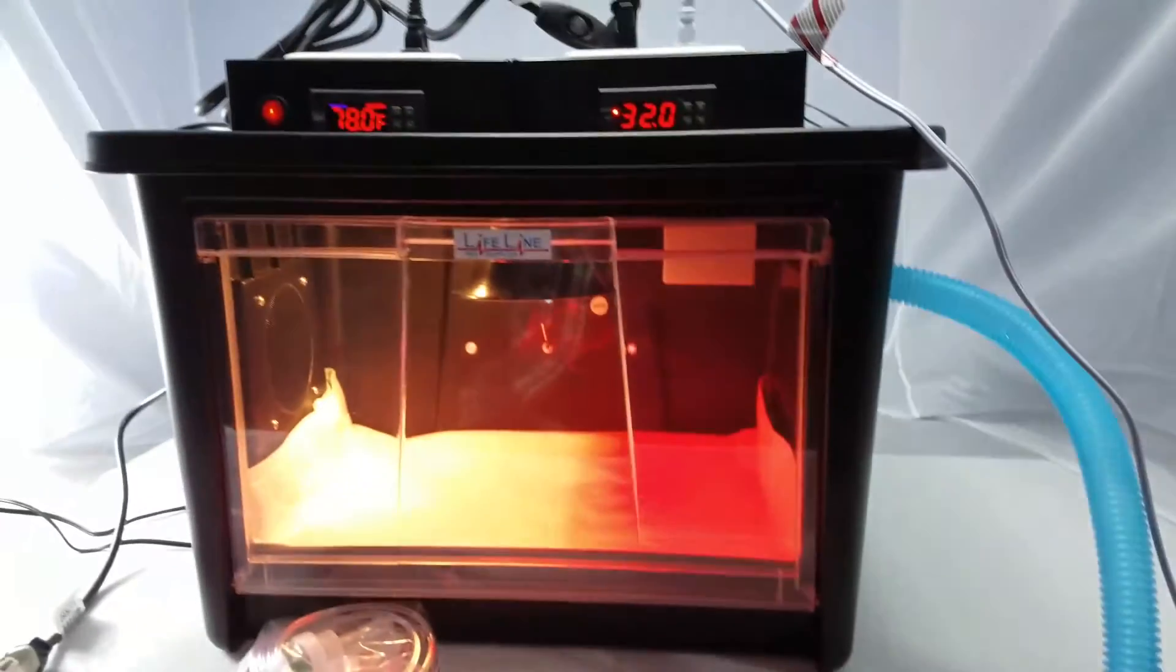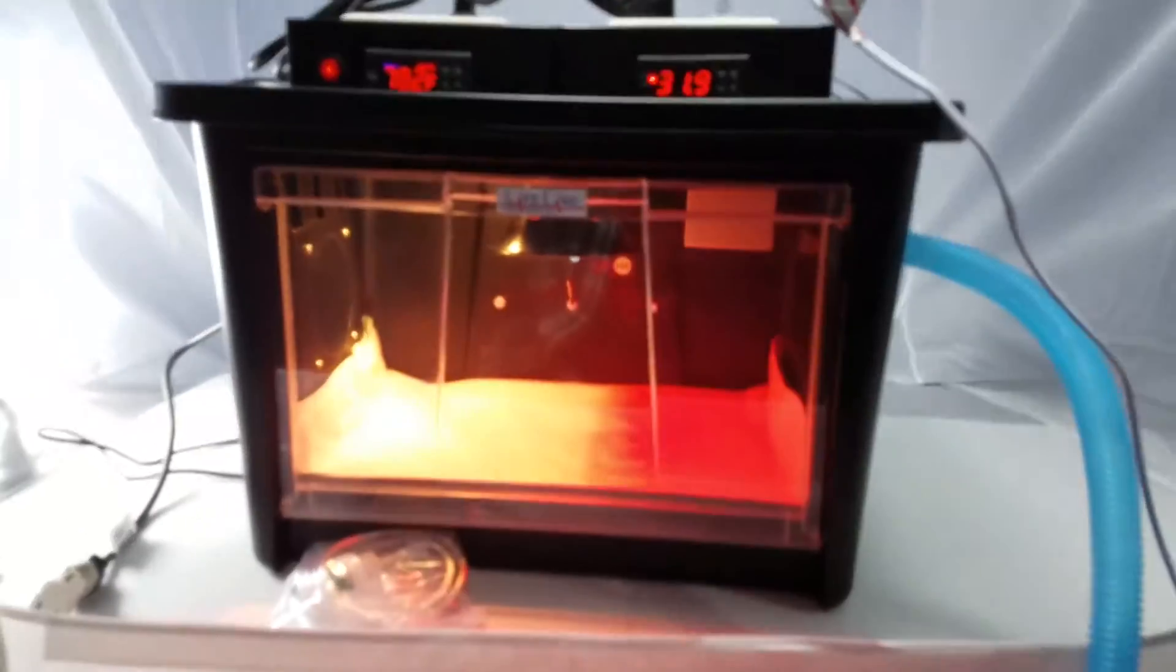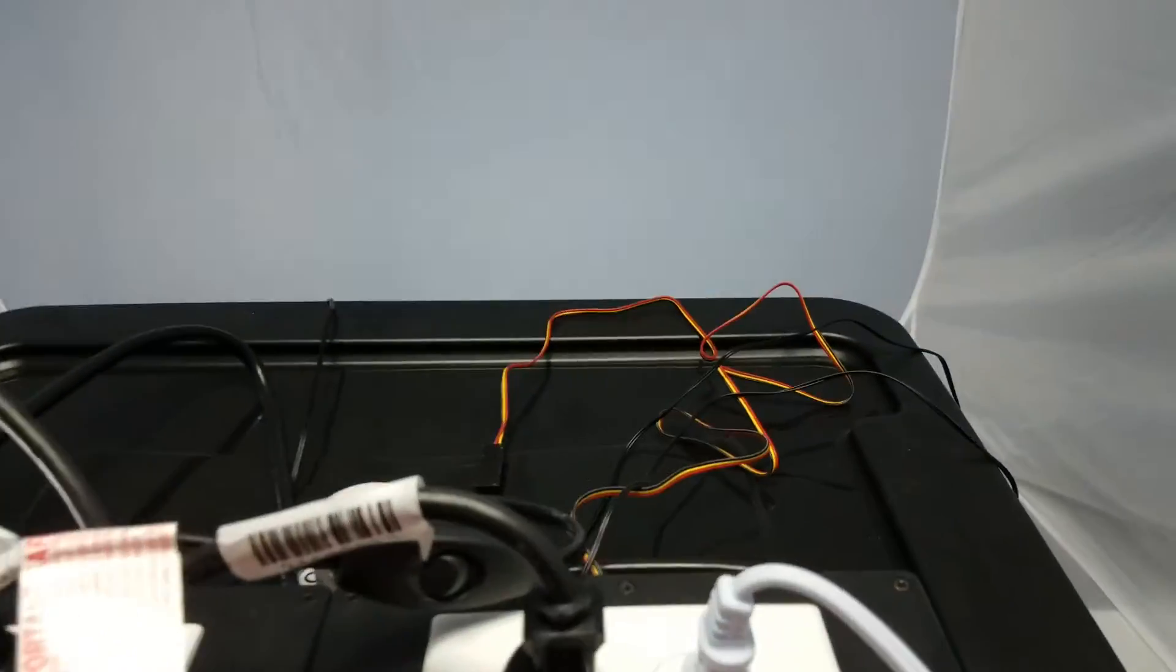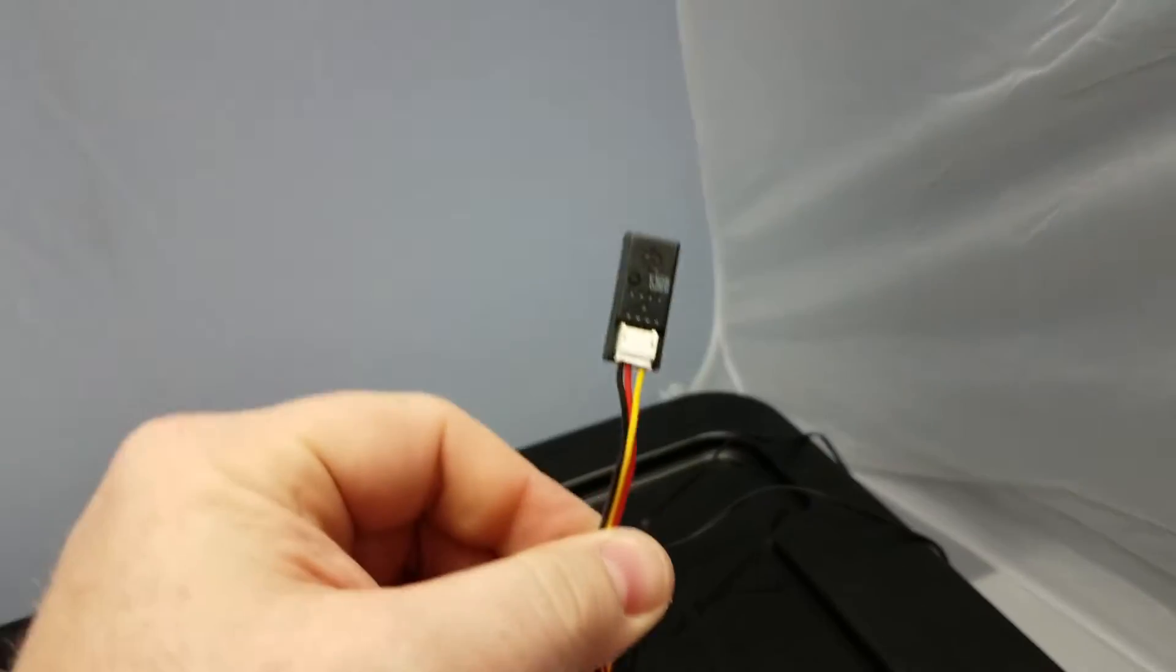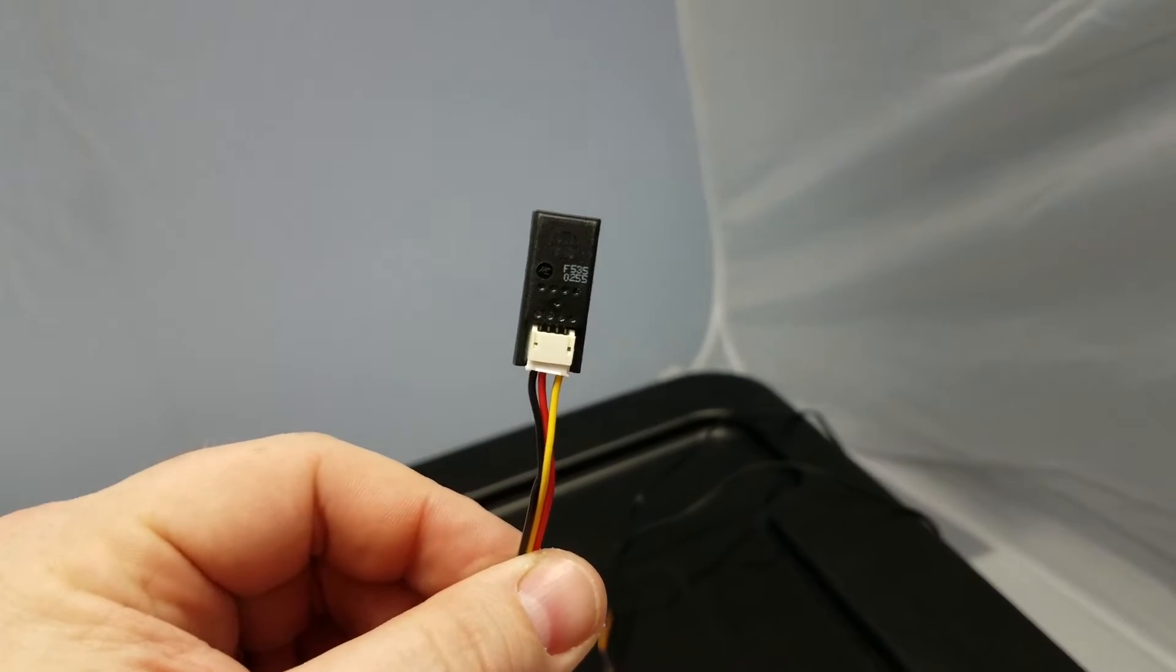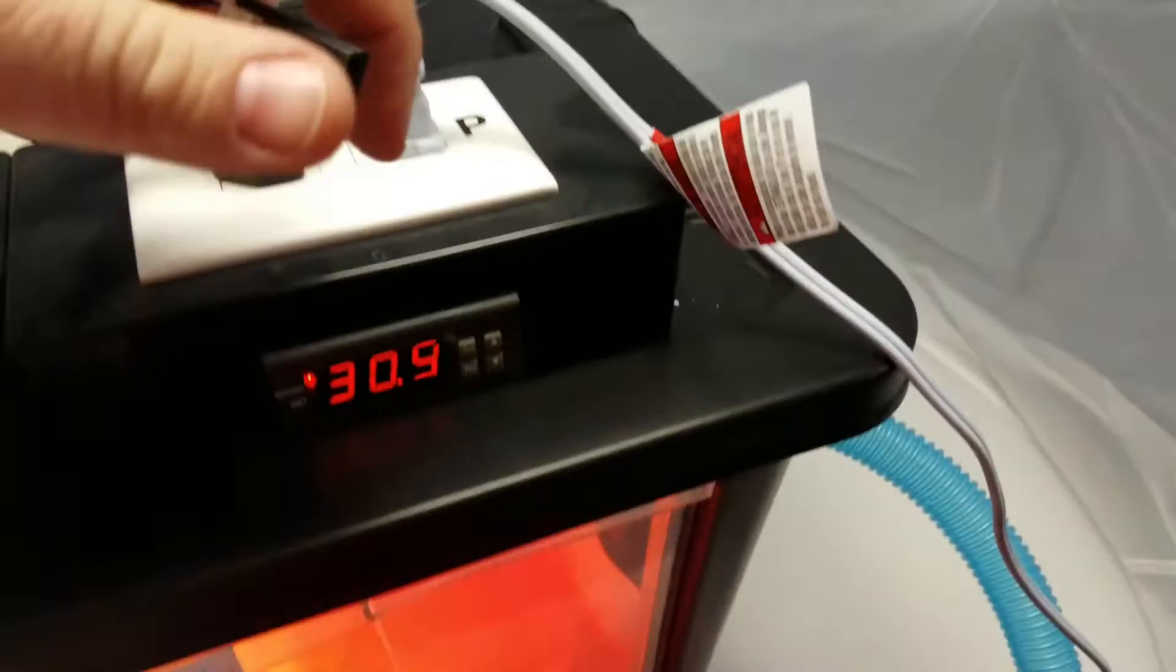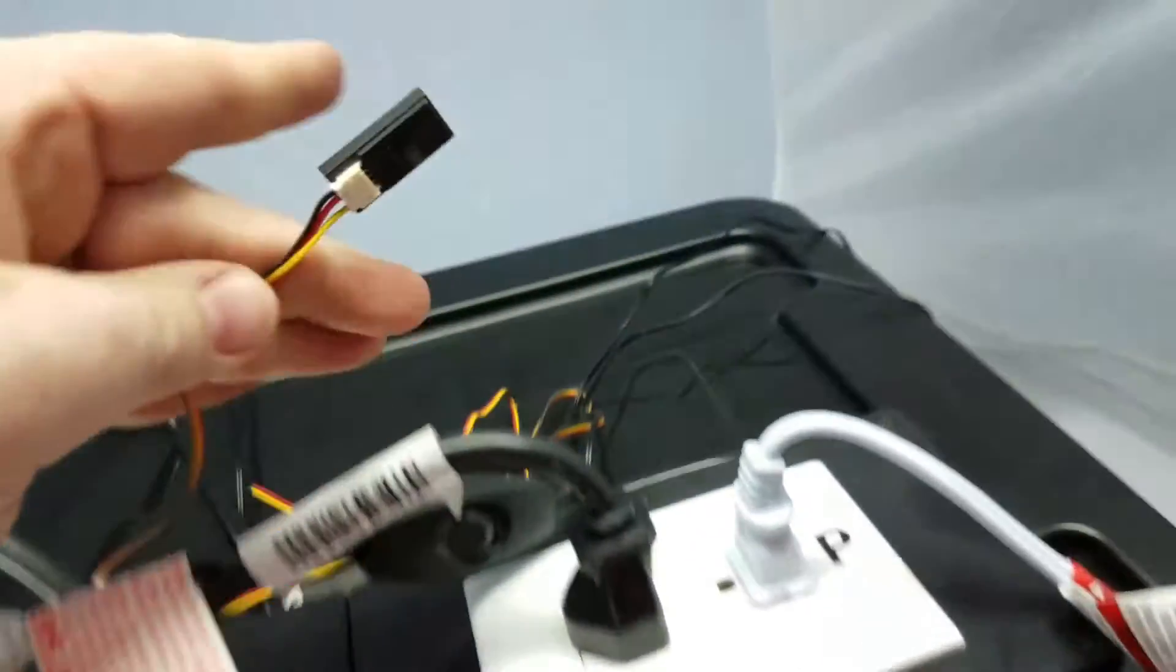Okay, we're back, and we've got that on the floor now, so that's running at a decline, as you can see, back to the pump there, and it is pumping humidity into it. But what we need to take a look at is actually our two sensors that come out of the back of the unit. So you have one that has a yellow, red, and black wire—that is the actual humidity sensor. If I hold that here, I see that humidity start to rise quickly because it's picking up the moisture here.